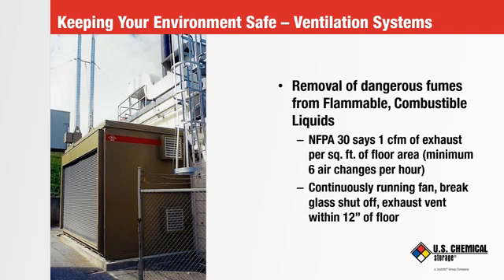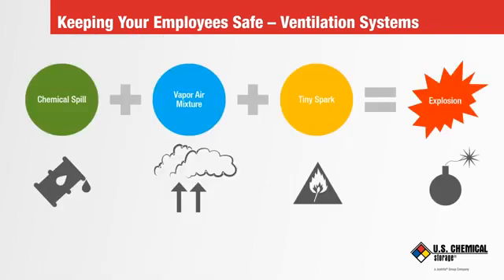This fume is usually heavier than air and will drift down, adding to the total fume accumulation across that flat sump floor. The fumes will begin to rise upward past the elevated flooring. If the fume-air mixture reaches a particular percentage depending on the chemical, it is susceptible to ignition by flame or spark. If ignited, an explosion in the building will occur. Ventilation is a solution.